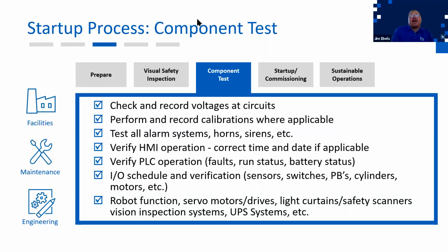And verifying HMI operation, making sure that it has the correct time and date where applicable, and the screen is functioning and displaying properly. Verification of the PLC operation, making sure there aren't any faults or run status or battery status issues. I/O schedule and verification in terms of inputs, so your sensors, switches, push buttons, make sure they're recognized and operating properly, as well as any cylinders, motors, etc.